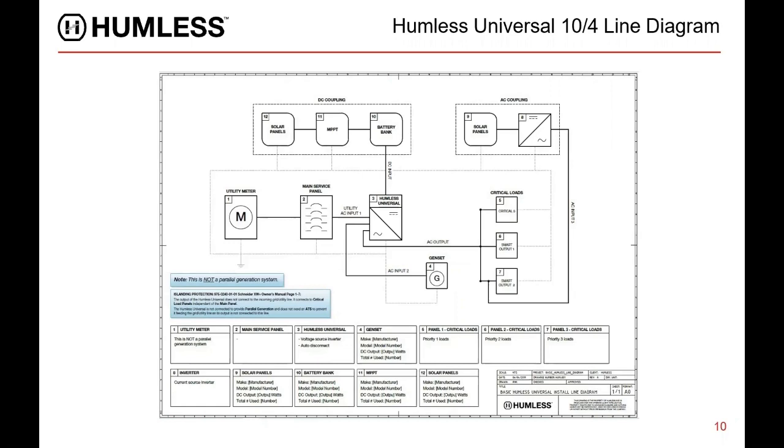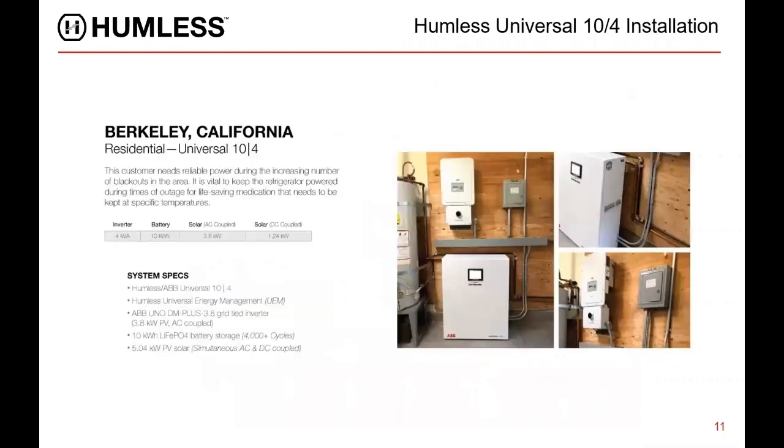The smart output you're seeing there following the AC coupling over here to the lower right, that's a bidirectional output that we use to control that SMA, that SolarEdge, that Enphase system at grid failure or off grid, by the way. I've got some great Enphase and SMA systems that are completely off the grid, allowing that AC and DC coupling just to be a feature for customers.